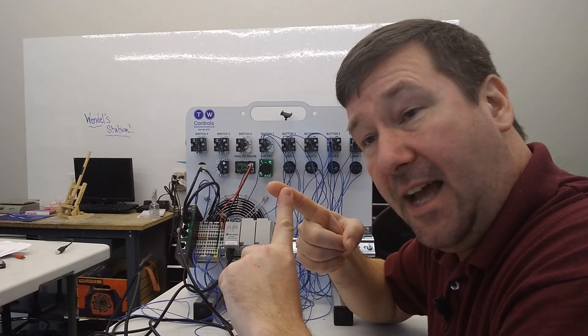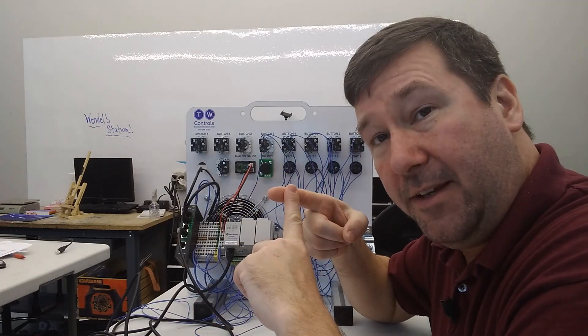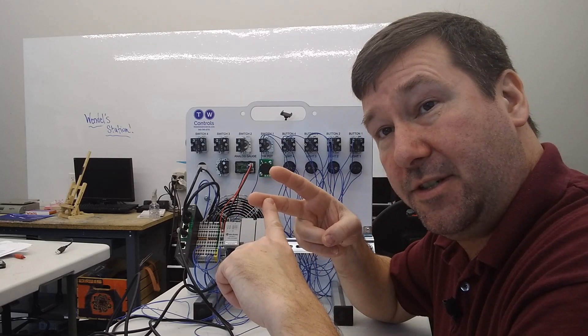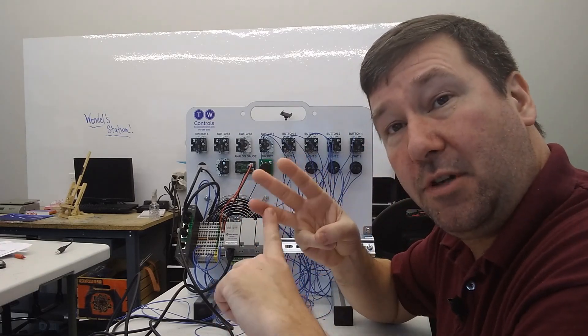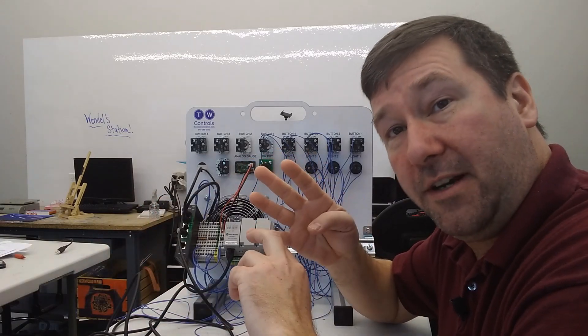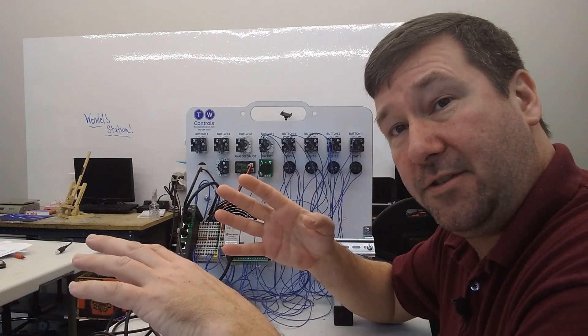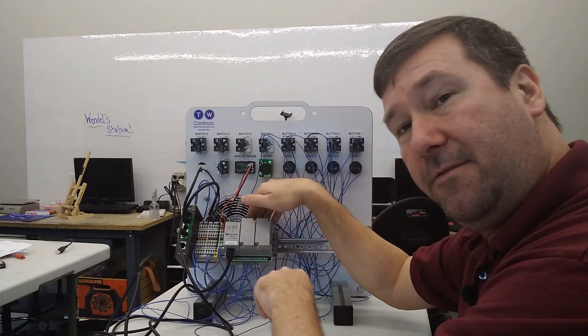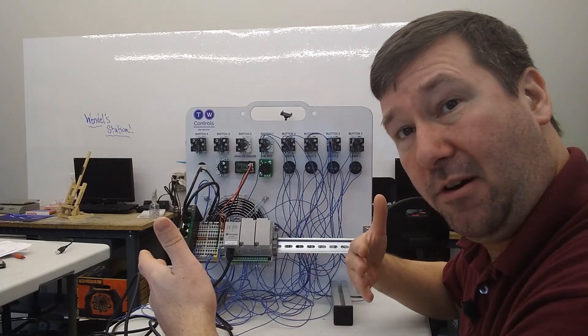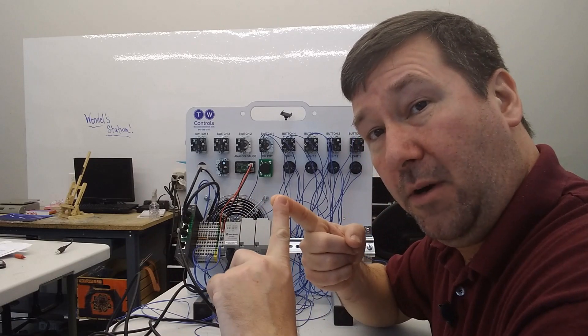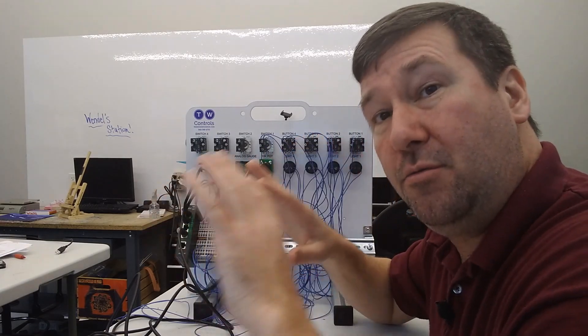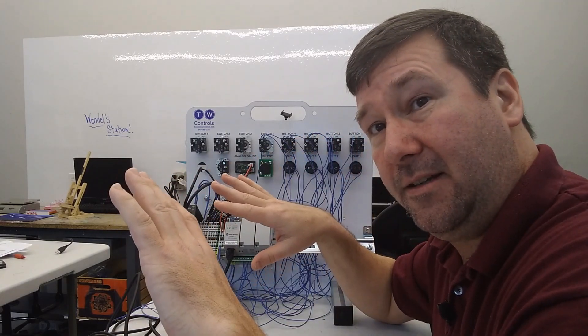So remember: a Direct Contact goes and looks for a 1 at whatever address you have in that instruction. A Reverse Contact goes and looks for a 0. A coil with true conditions will write a 1 to whatever address you have in that instruction, and a false coil will write a 0. And remember, it only writes to the variables — it does not read physical inputs or write to physical outputs during program execution. That is done during the input and output part of the scan cycle. If you stick to 'go look for a 1, go look for a 0, go write a 1, go write a 0,' then you will be hours — maybe years — ahead.